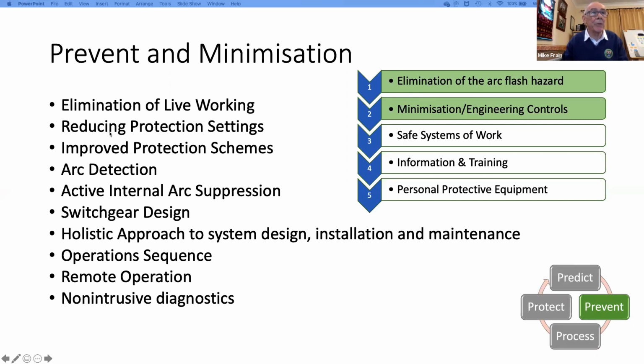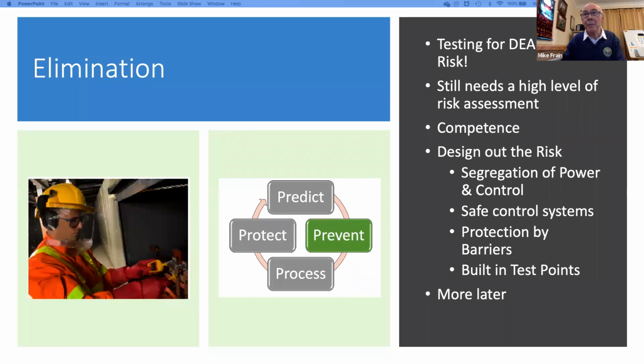First one's elimination of live working. Reducing protection settings, I've got a little bit to say about that. Improved protection scheme, something I could highlight. Again, it's in my book, in the guide, so there's quite a lot on that. Arc detection, active internal arc suppression, and I've got a slide on that. Switchgear design, holistic approach to system design, and operation sequence, a slide on remote operation and non-intrusive diagnostics. So there's a lot there which I'm not going to hope to cover tonight. So you'll just bear with me, I'm sure, to try and go through this as quickly as I can.